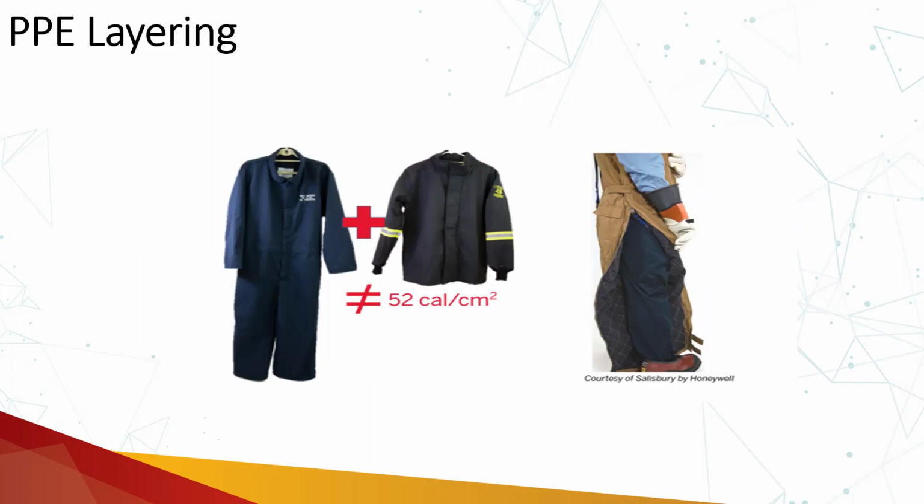But you have to make sure, for this particular PPE which they are wearing, what the ATPV and EBT against which it is tested. On the other type of personal protective equipment which are available now mostly in the field and industry, that mentions the calories per centimeter square. So there are PPEs which are rated for 100 calories per centimeter square as well, 100, 110, 120.